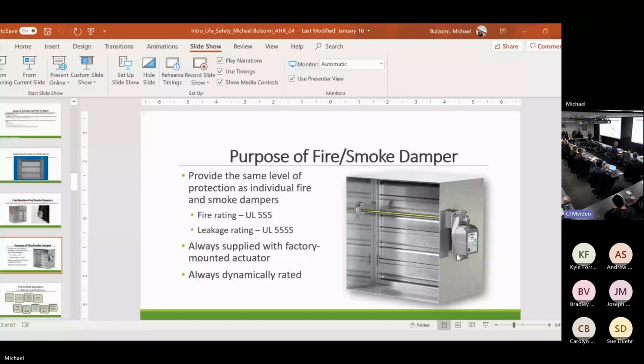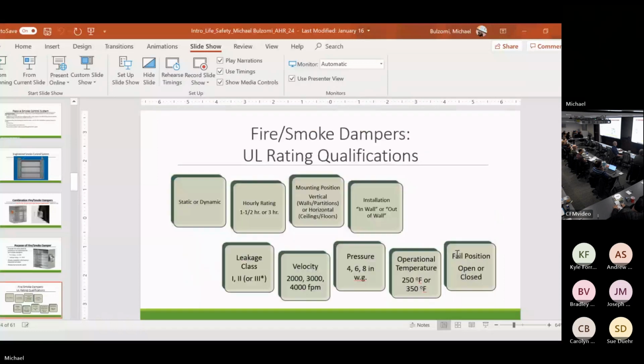And as a damper manufacturer, I got a lot of requests. Can you just ship all the dampers without actuators, and we'll put the actuators on when they come in? If you were ever told by a contractor or a manufacturer that they will do that, ask them to put that in writing. They won't, because they're not allowed to. They're not allowed to ship a damper without a factory mounted actuator. One particular manufacturer is doing it. That's why I bring it up. They didn't want to lose the job.